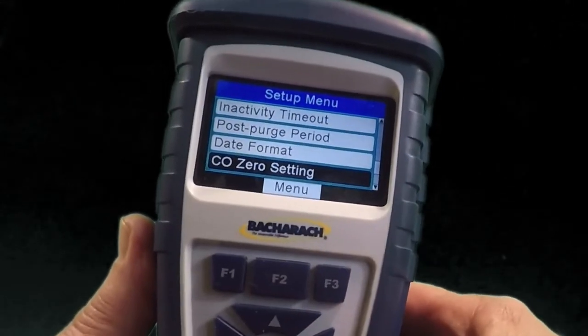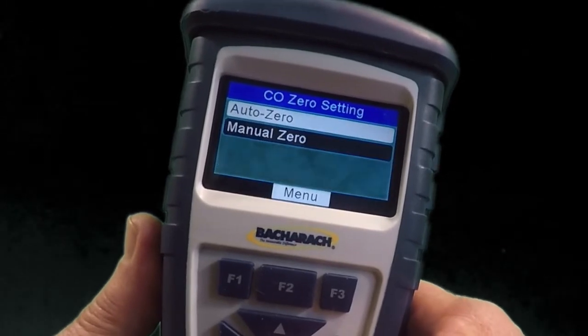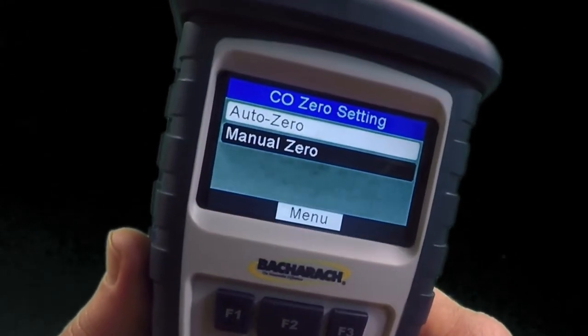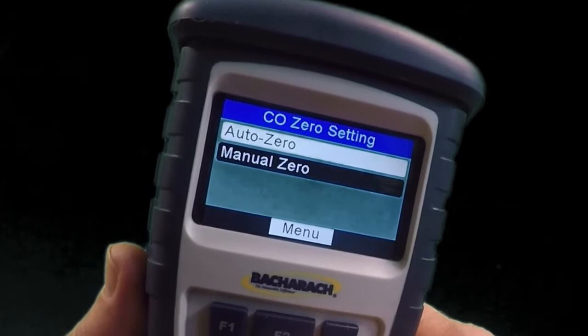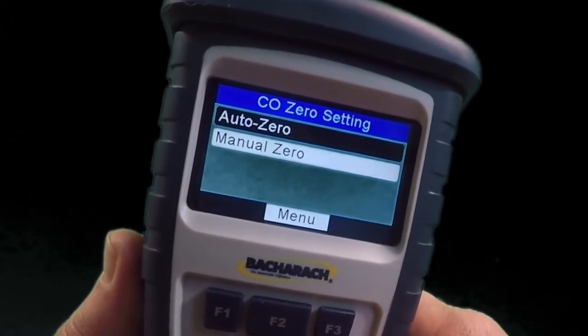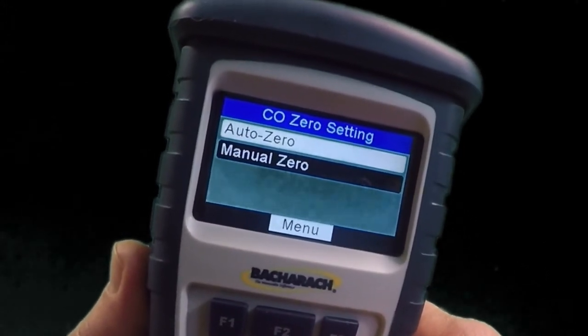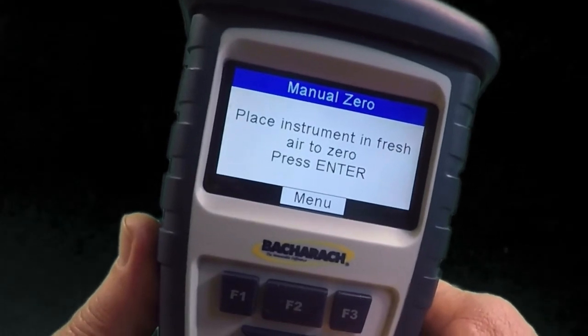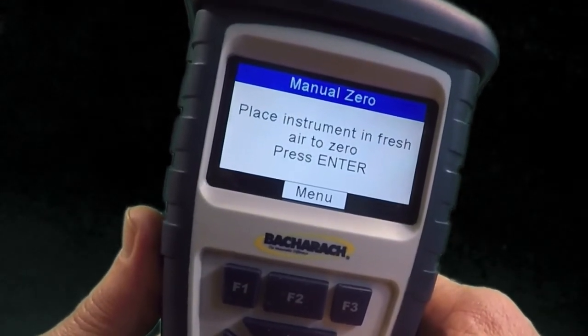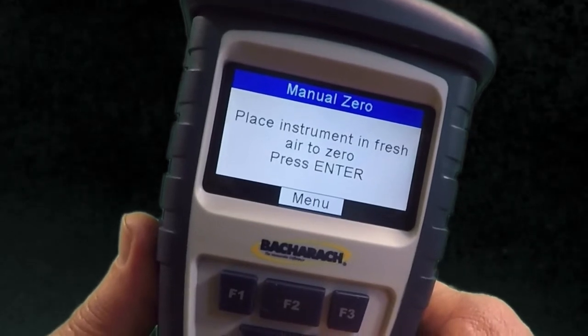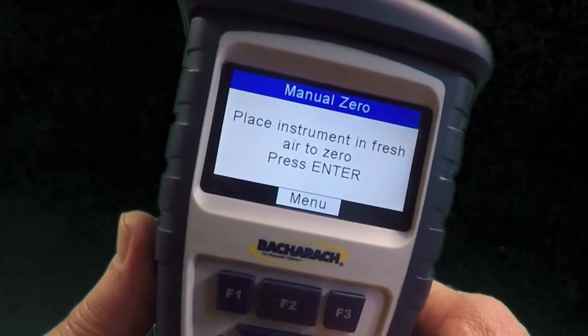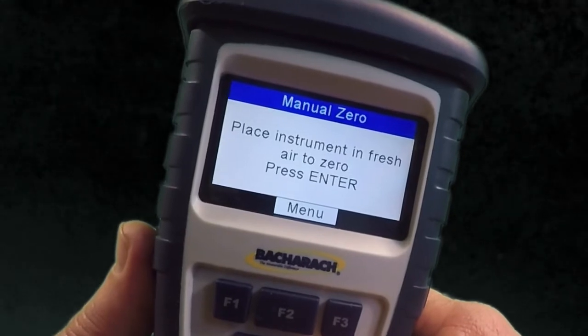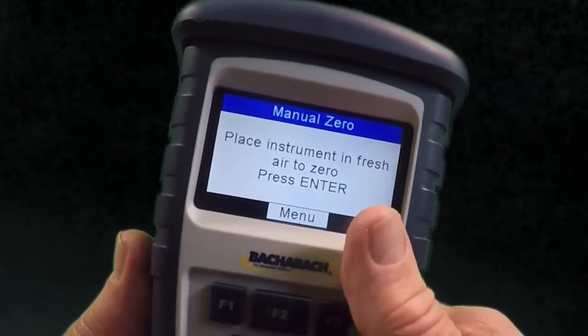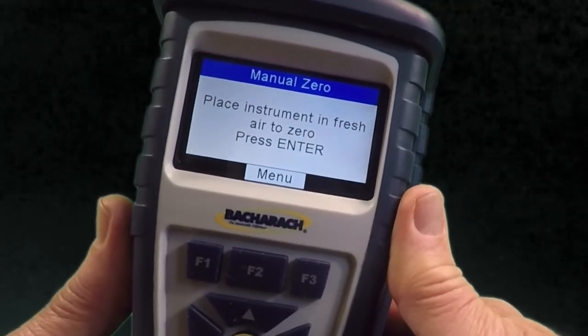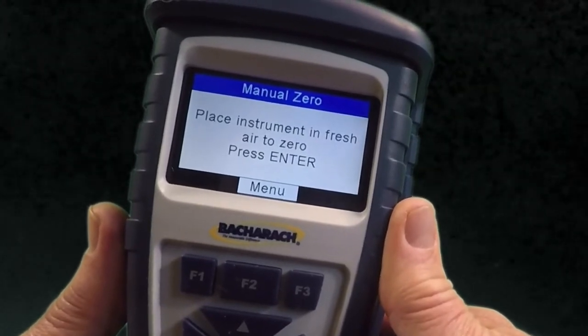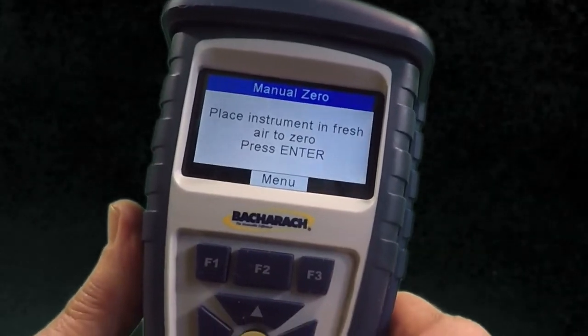To set for a manual 0, you'll hit enter. Okay, you'll see manual 0, that's what I've got this one set up for. So let's say you turned it on and it said auto 0. What I would do is select manual 0, hit the green enter button, and then it says place instrument in fresh air, so you'd want to go outside, hit the button again. The display will read setting manual 0. The pump will run for 60 seconds and the manual 0 will be stored. I've had a lot of experience with that manual 0 reading. It's very accurate. So we'll back out of that.